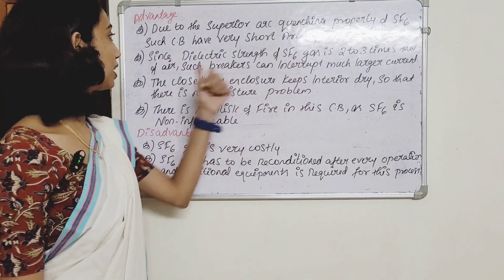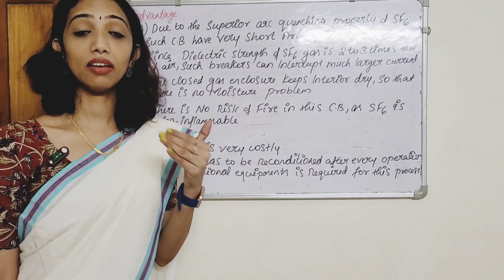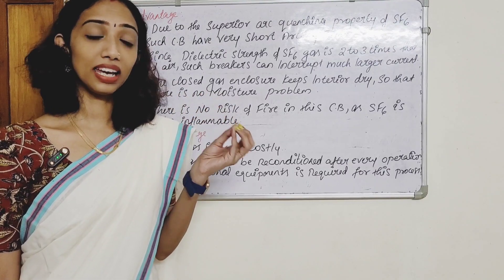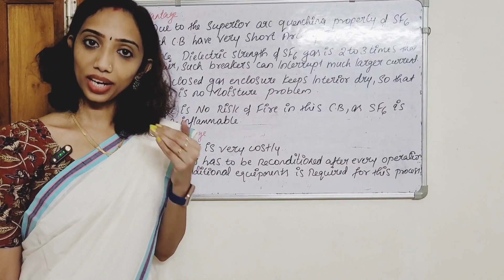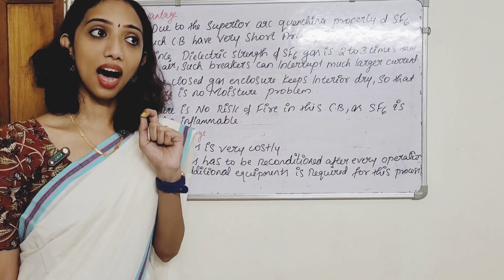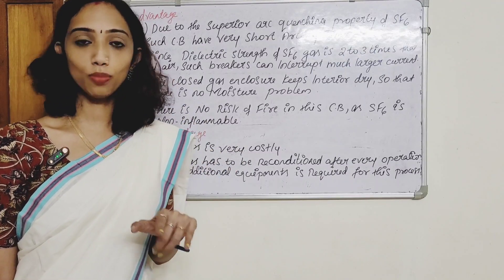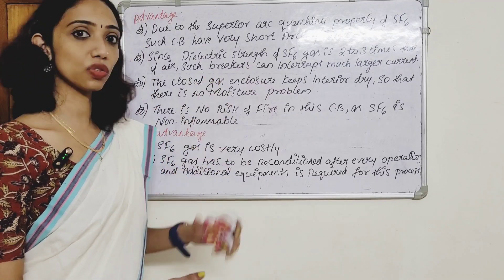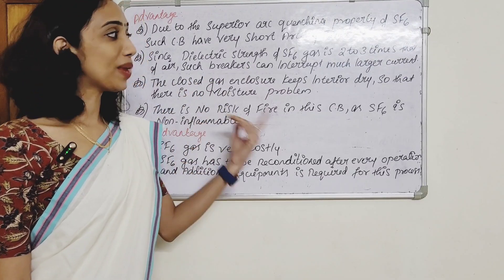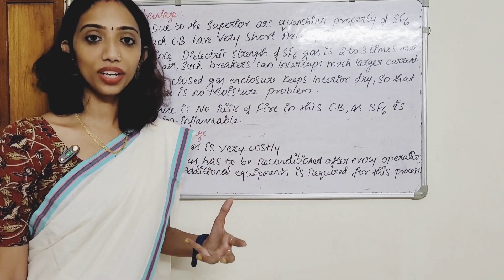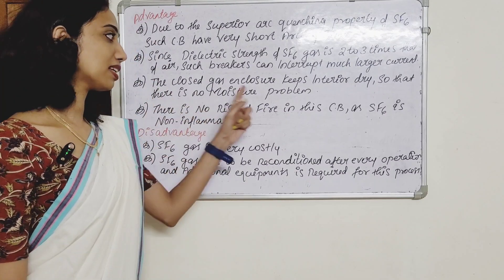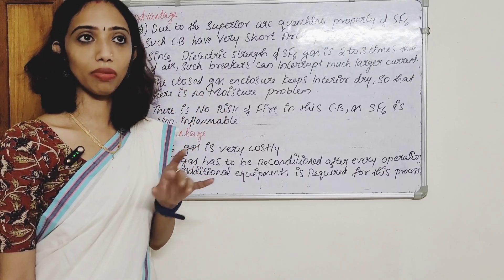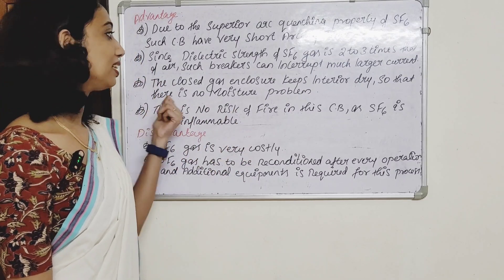Since the dielectric strength of SF6 gas is 2 to 3 times that of air, such breakers can interrupt much larger fault currents. When the moving contact breaks away, the arc forms, but the superior dielectric strength of SF6 means it is quickly extinguished. The closed-gas enclosure keeps the interior dry, so there is no moisture or rusting problem.